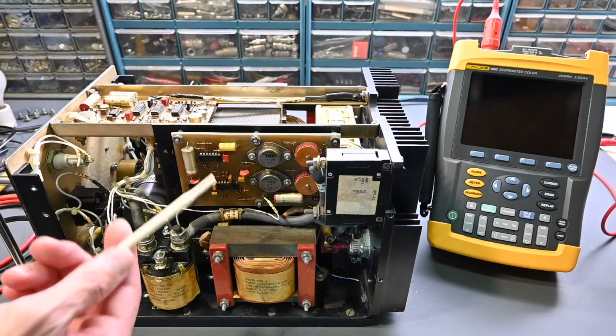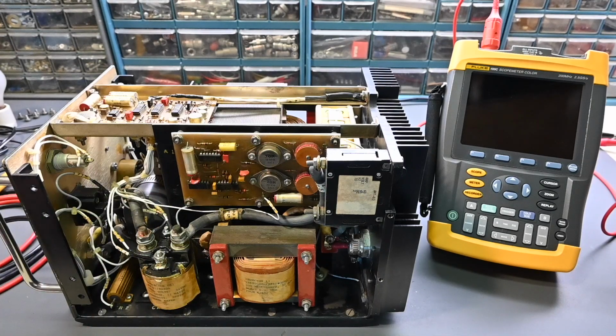When the frequency came up, the output voltage came up as well, which also makes sense. Now the output voltage is about 119 volts under no load, and when I put a 300 watt load on the inverter, it dropped to about 117 volts. This is rated for 115 volts output, and it probably falls to that at full load, so things are looking very good.